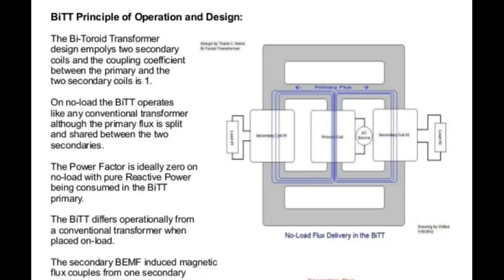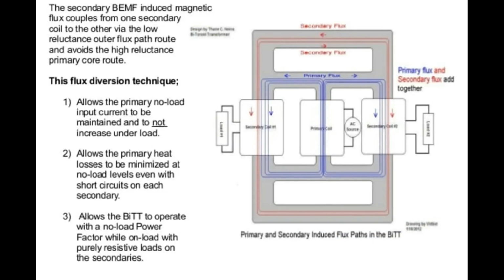the bitoroid transformer primary. The bitoroid transformer differs operationally from a conventional transformer when placed on load. The secondary back electromagnetic field induced magnetic flux couples from one secondary to the other via the low reluctance outer flux path route and avoids the high reluctance primary core route. This flux diversion technique allows the primary no-load input current to be maintained and to not increase under load.